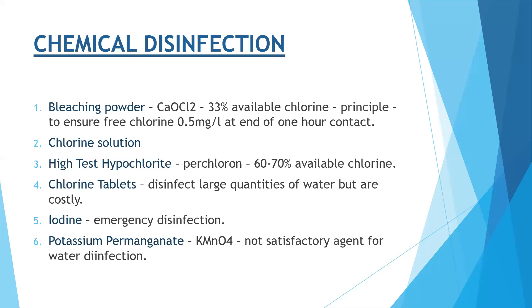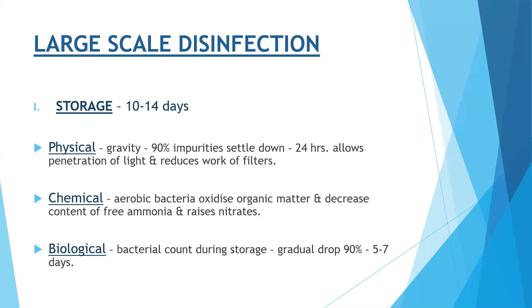Moving to large-scale disinfection, which consists of three steps: storage, filtration, and disinfection. Storage takes around 10 to 14 days. Under physical means, gravity allows around 90% of impurities to settle in about 24 hours, allowing light penetration and reducing filter workload. Chemically, aerobic bacteria oxidize organic matter, decrease free ammonia, and raise nitrates. Biologically, bacterial counts drop by around 90% in 5 to 7 days. The whole storage process takes 10 to 14 days.